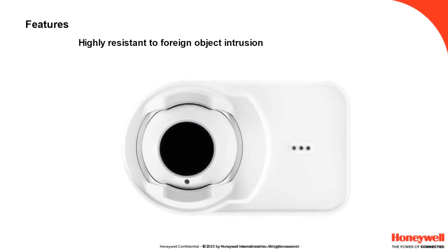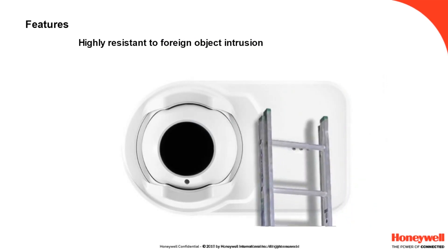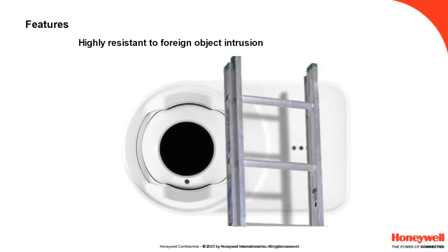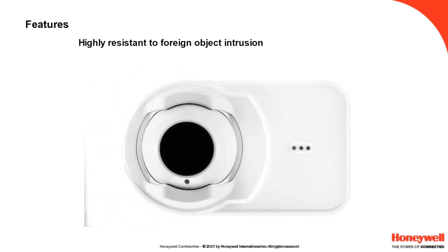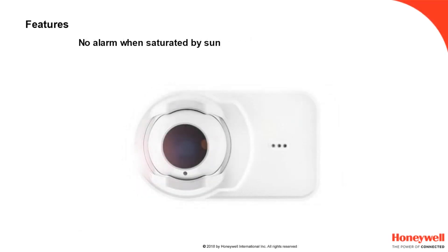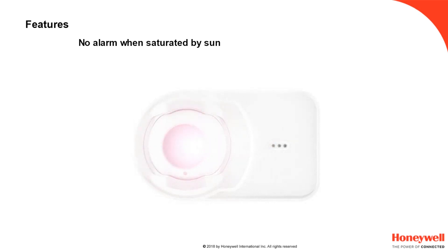The detectors normally operate in the ceiling space of the building and so generally they will be out of the way of most obstructions, but not all. The device is calibrated to ignore transitory obscuration. If the obscuration is sufficient and persists, the device will go into a fault. Using the CMOS imager, the device is very resistant to external light sources, including bright sunlight — a common failing of traditional beams.